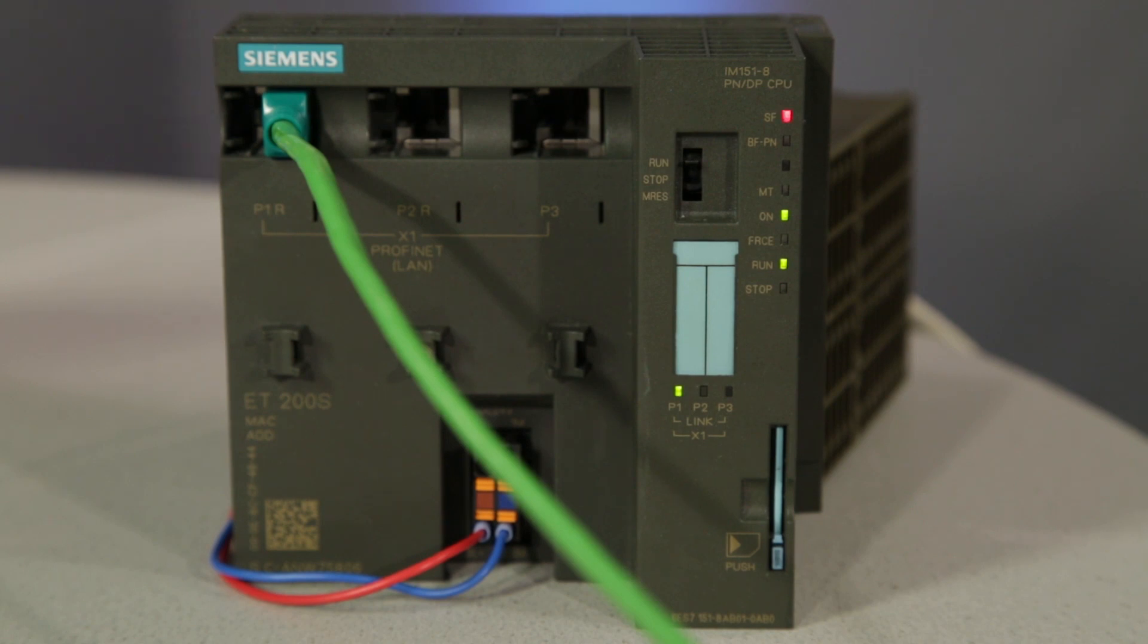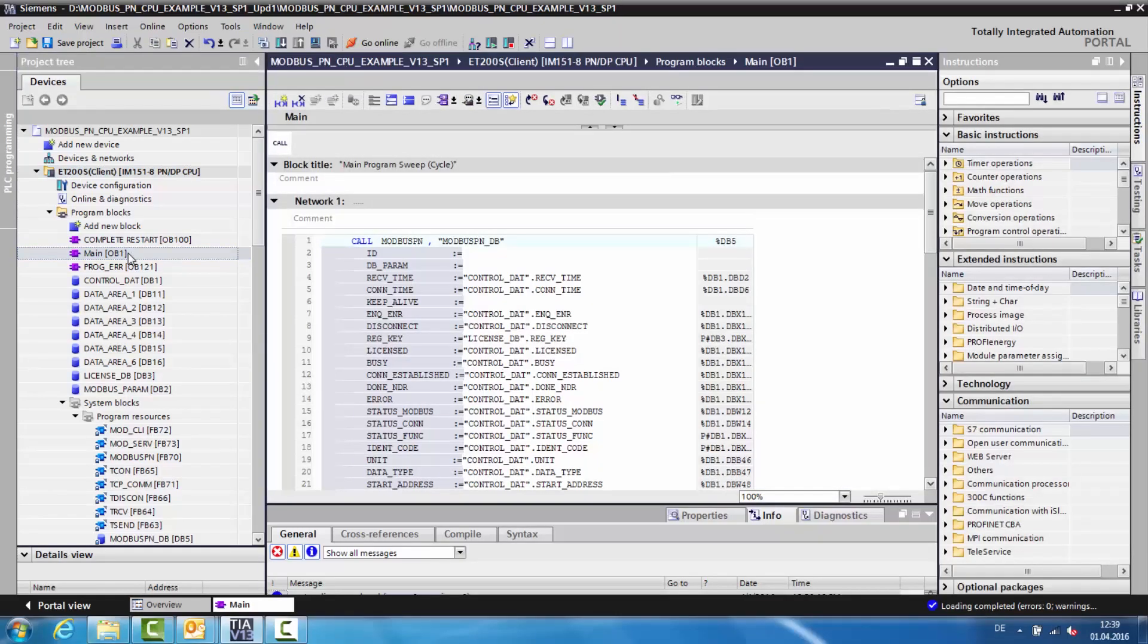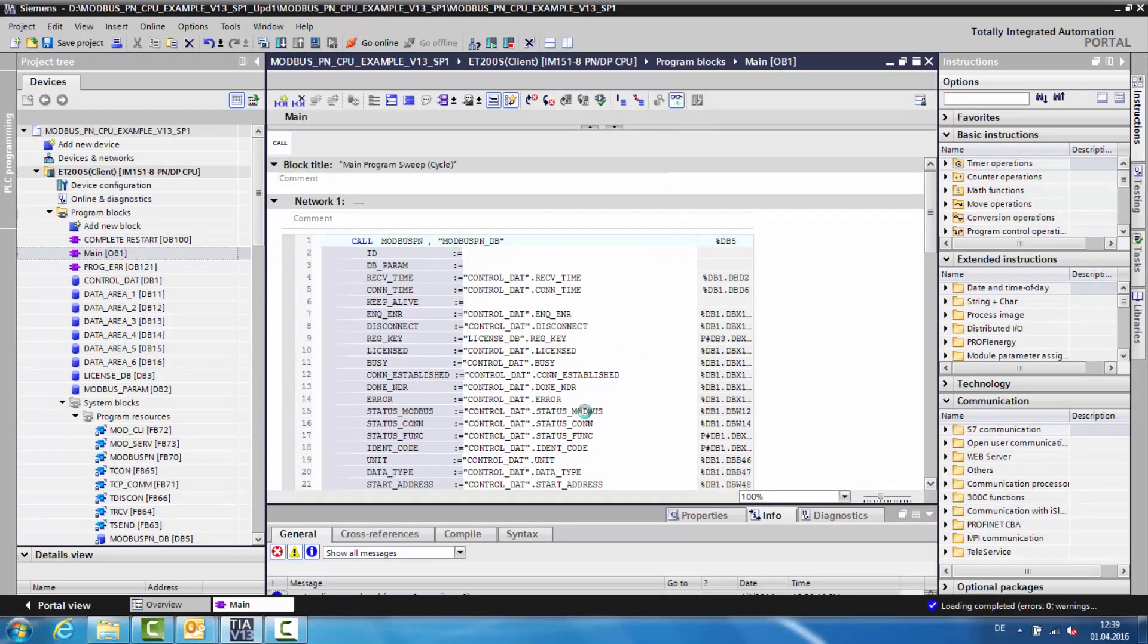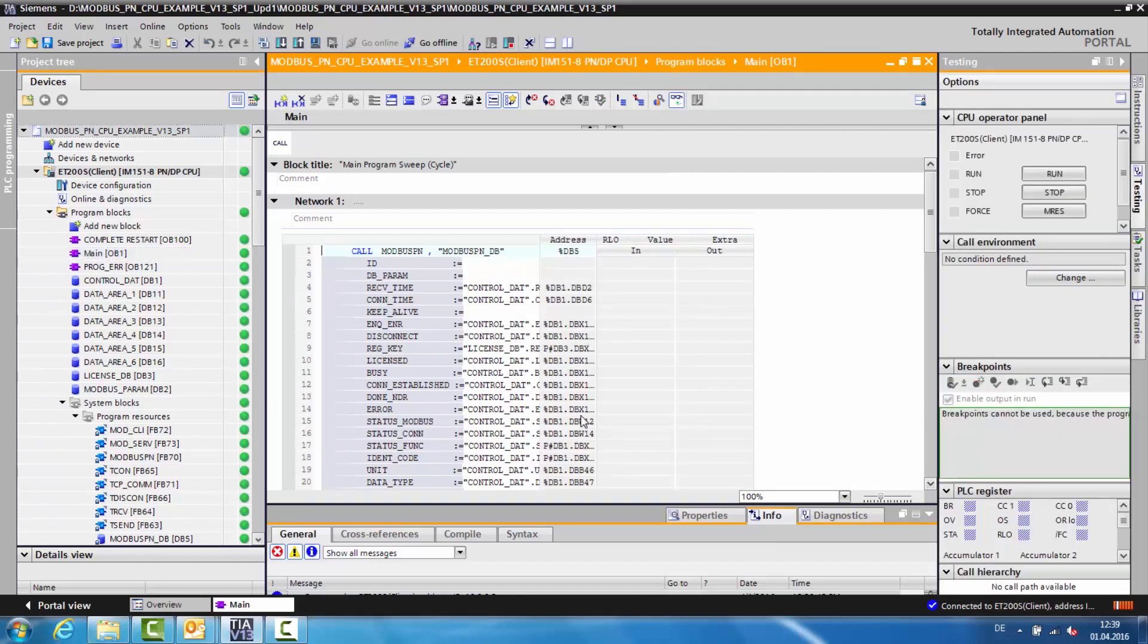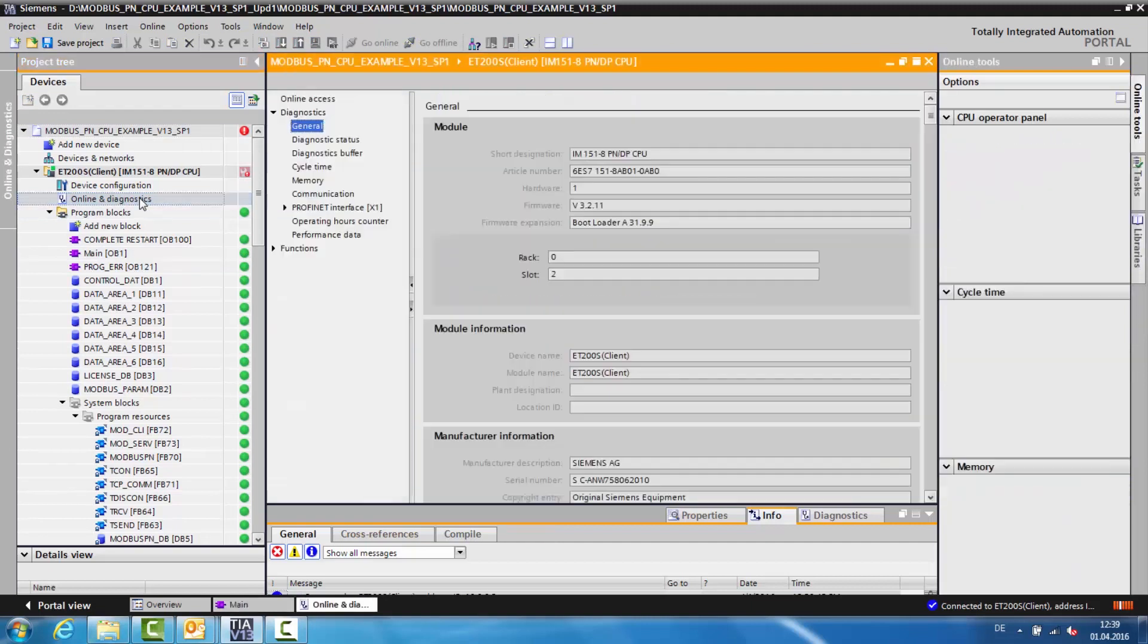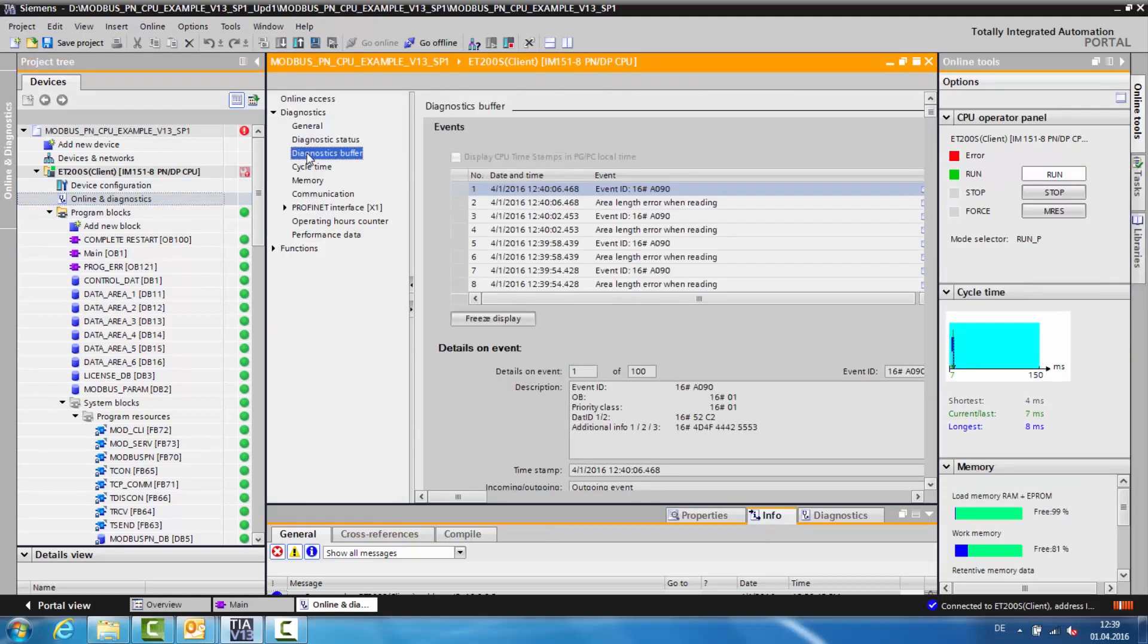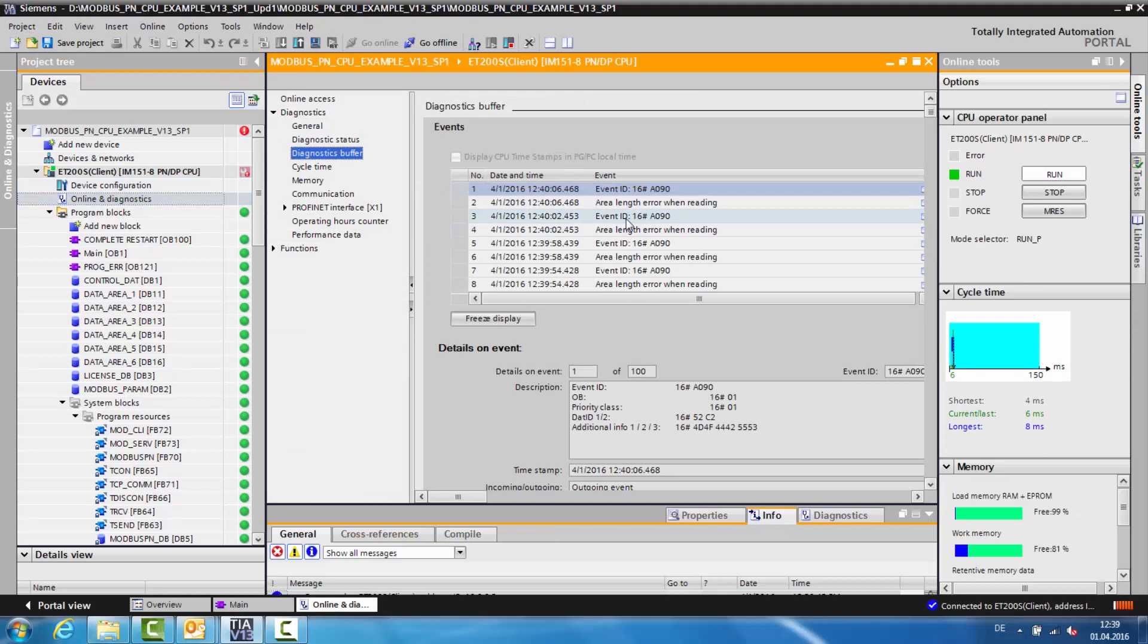The first sign is a blinking LED on the CPU. The second indicator is the information A090, as seen on the block output status Modbus. This status information A090 will also be visible in the diagnostics buffer of the CPU.